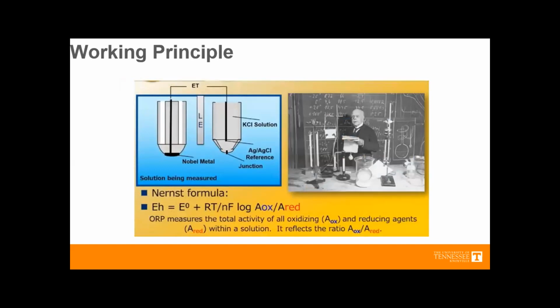This is kind of how a working probe would work. You've actually got two separate electrodes. One is going to be a noble metal electrode, and the other is going to be a reference electrode. That's going to be governed by the Nernst equation right here. So the math that you're going to get when you go through it empirically, determining all of your voltages and measurements and correlating them, is going to follow this equation.